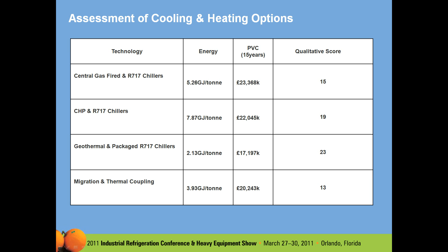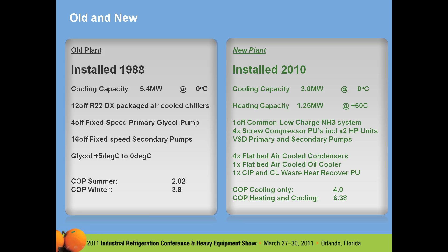Now, it's quite embarrassing when you make somebody a promise and then get it wrong. In this case, we promised them they wouldn't use too much extra electricity by recovering the heat. It's good science - if you throw heat away at 40 degrees versus recovering it at 60, you should expect energy consumption to go up. Just the reverse of what was said earlier about getting the head pressure down. It should go up. We promised them it wouldn't go up too much.